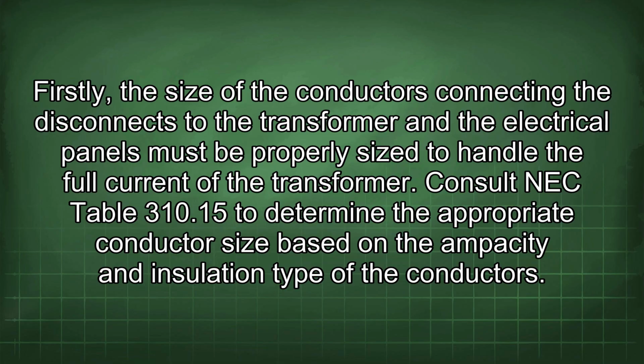Firstly, the size of the conductors connecting the disconnects to the transformer and the electrical panels must be properly sized to handle the full current of the transformer. Consult NEC Table 310.15 to determine the appropriate conductor size based on the ampacity and insulation type of the conductors.